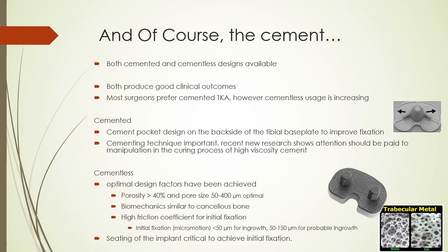We want a high friction coefficient for initial fixation, and we know the criteria for good ingrowth from the fixation micromotion standpoint. And also through research, we know that the initial seating of the cementless device on the bone is very, very critical. We want to always ensure a full seating for better initial fixation and ingrowth.